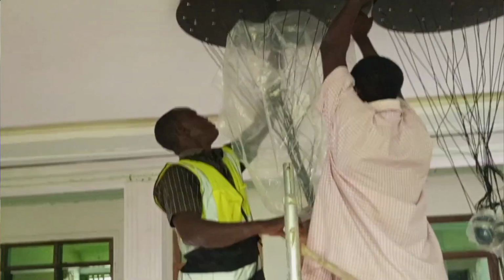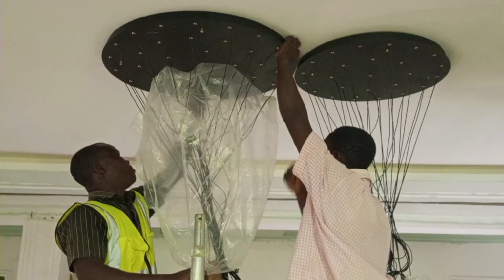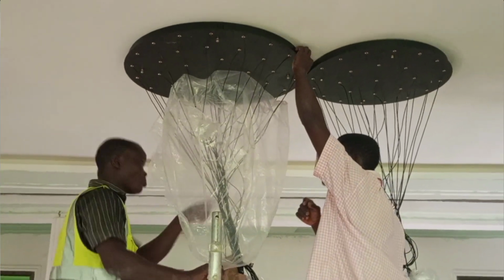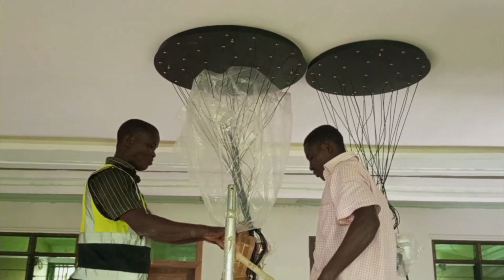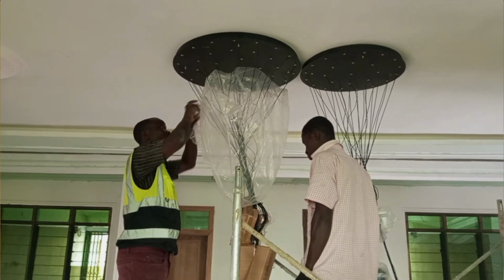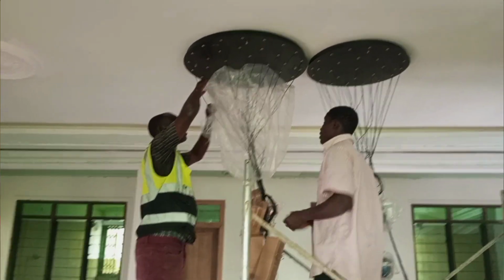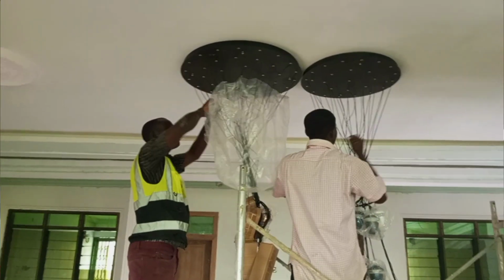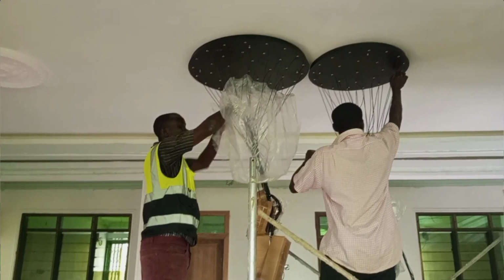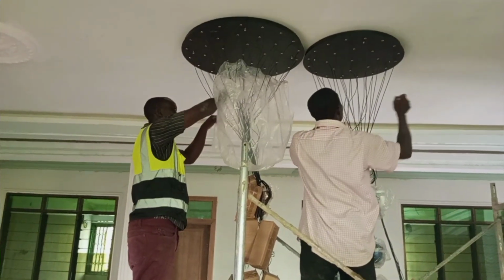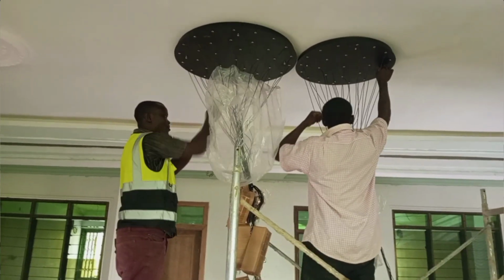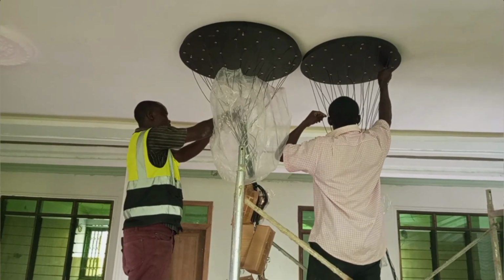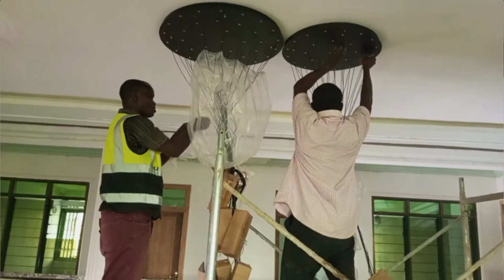All right, so in the same way, you can have just one hole, but depending on the type of chandelier you are going to use, by the time you have done your calculation properly, you realize that putting the loads in that hole on a 6 amp breaker would just be a nuisance. So even when there is no fault, your breaker will keep tripping because the total load will now be more than the size of breaker that you are using. All right, so I believe this is going to help you a lot in your next electrical wiring.